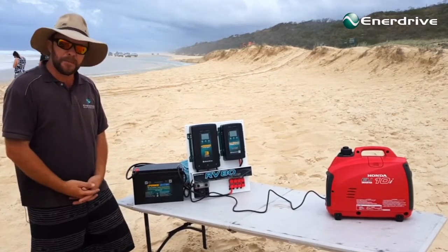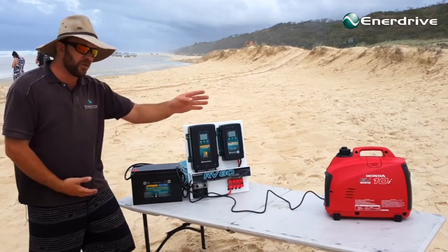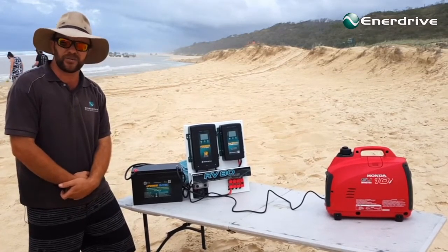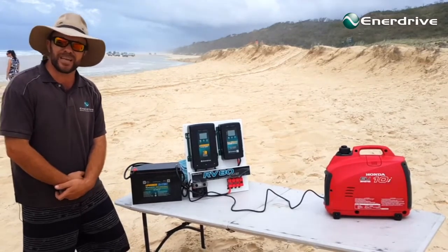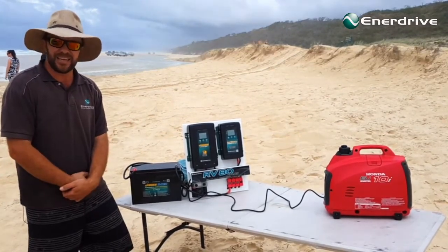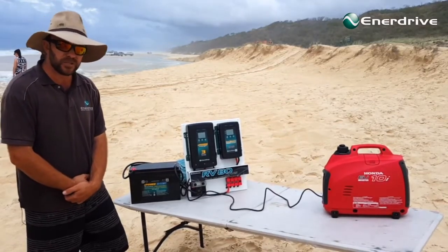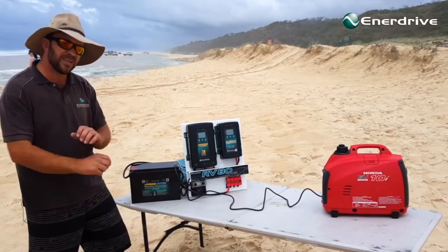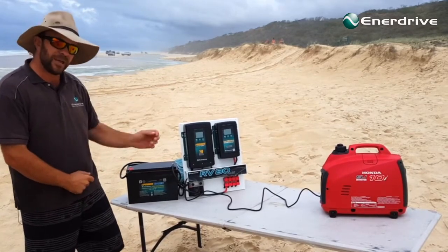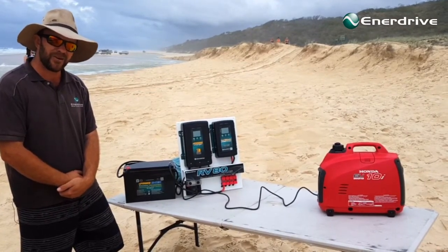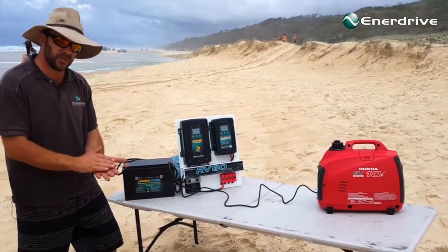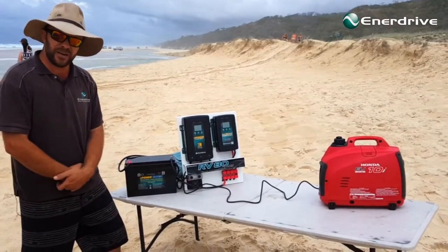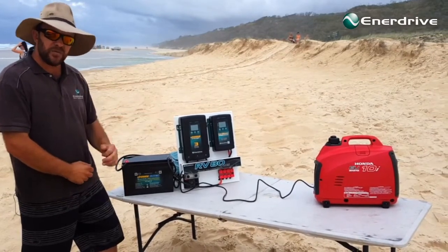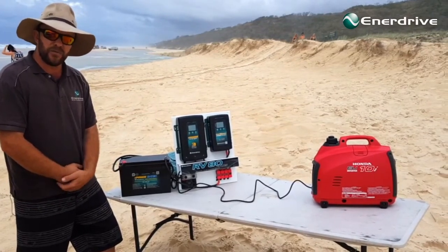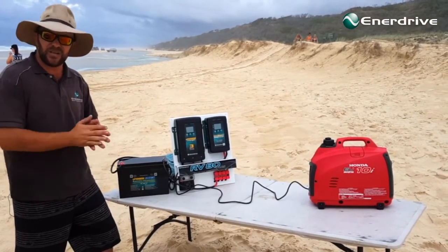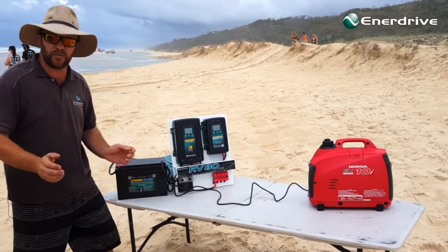Well, I'll tell you. Most people using these chargers and relying on generators are also relying on their generator for other loads - that could be as simple as running air conditioning, which it typically is. Now if you've got a 2 kVA Honda, a 2.2, or any other generator around those sizes, and you're trying to run a 40 amp charger at the same time as starting up aircon - and it starts up every time it cycles on and off, not just the first time - you're going to run into problems. With these chargers, you've got the best possible opportunity of easy use, no hassles, no need to turn the charger off before you start the air conditioning.